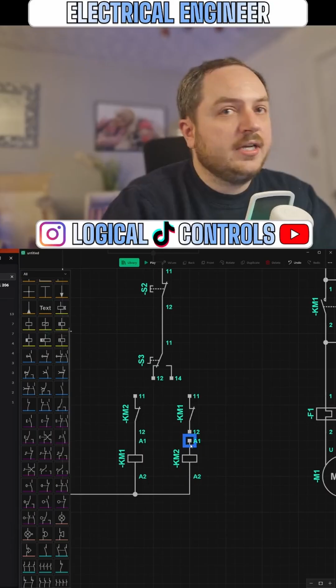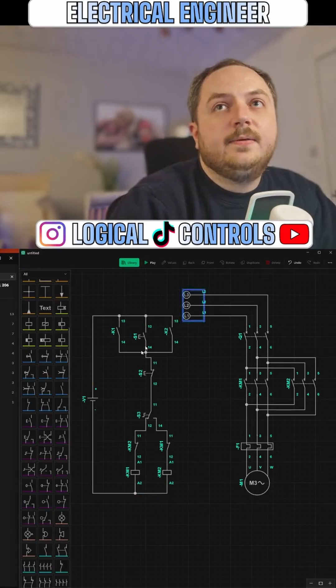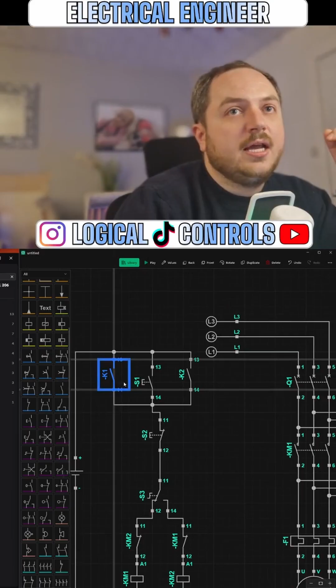Let's press play, let's push our start button. We're not holding in because I changed them to KM1 over here. They're now KM1, but I didn't change the latch to KM1. So there's a second auxiliary contact, that's a normally open auxiliary contact.